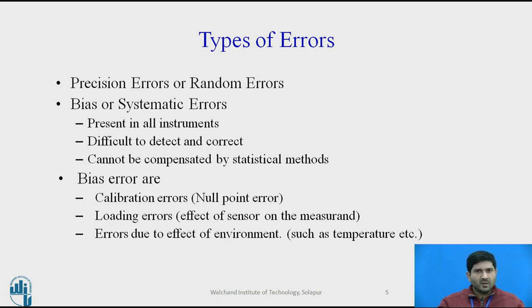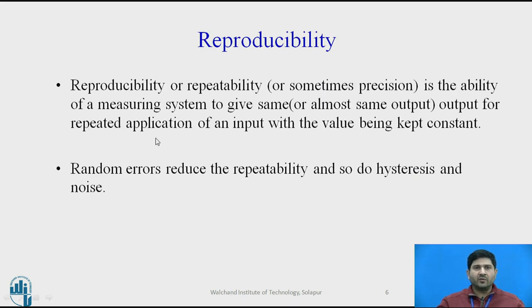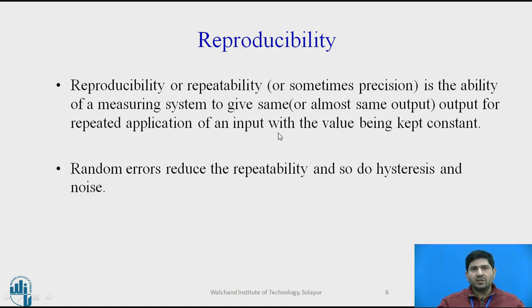Another important characteristic is often called reproducibility — some textbooks term it repeatability, and others use the term precision; they are often used interchangeably. It is defined as the ability of the measuring system to give the same, or almost the same, output for repeated application of an input with the value kept constant. Random errors reduce repeatability, and so do hysteresis and noise. If there is poor repeatability, you might want to check for hysteresis effects and associated noise, which to a certain extent can be compensated by using proper signal conditioning.